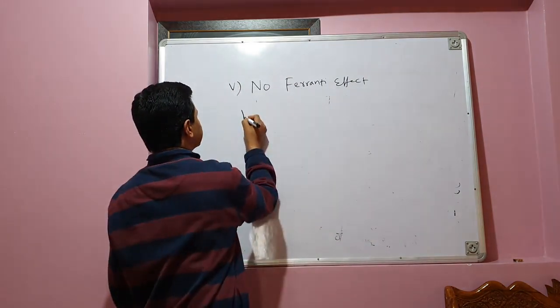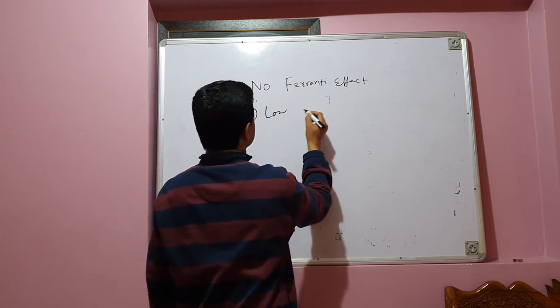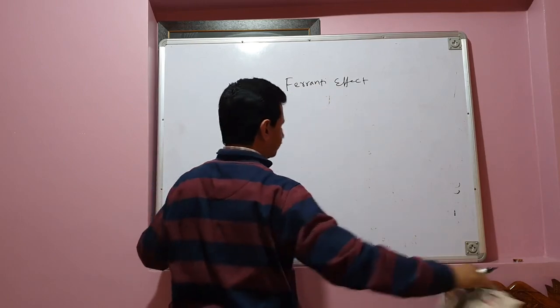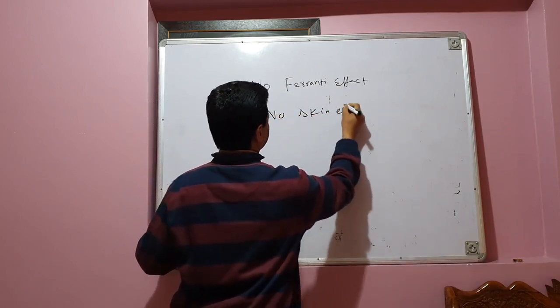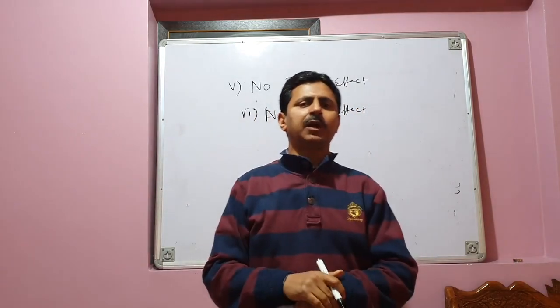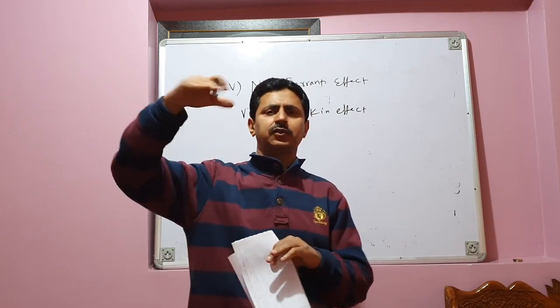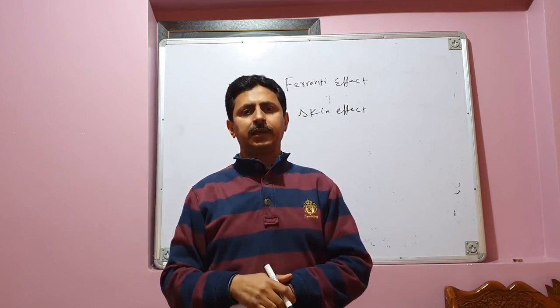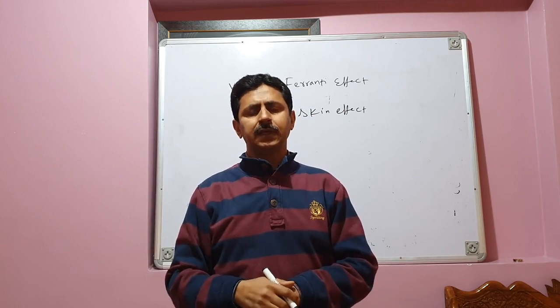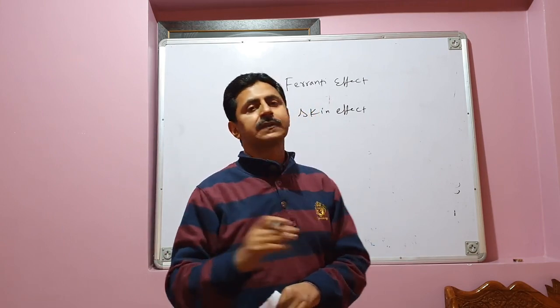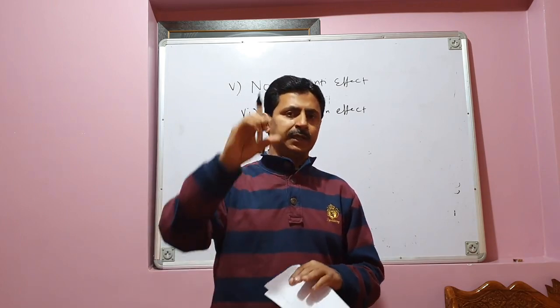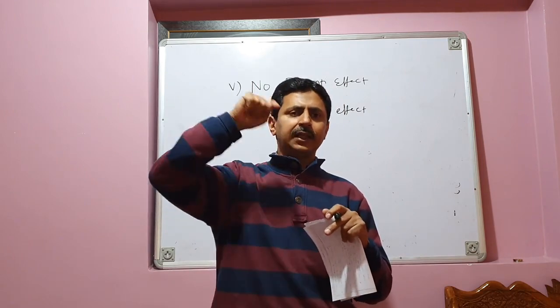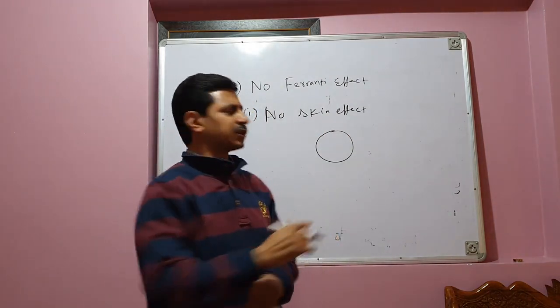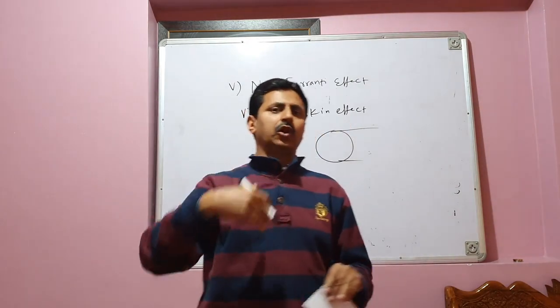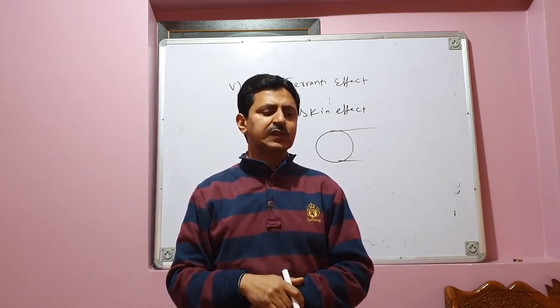Okay. Next is no skin effect. Again, you must be knowing about skin effect. Because of the skin effect, the current gets confined to the periphery of the conductor, and it increases the overall or effective resistance of the line, and copper losses increase. And this skin effect is absent in HVDC power transmission system. In HVDC, if this is the diameter of the conductor, the cross section of the conductor, the current is uniformly distributed throughout the cross section of the conductor, and therefore there is no skin effect. So skin effect is absent in HVDC power transmission system.